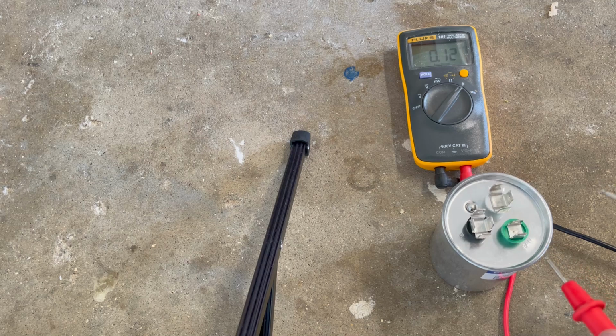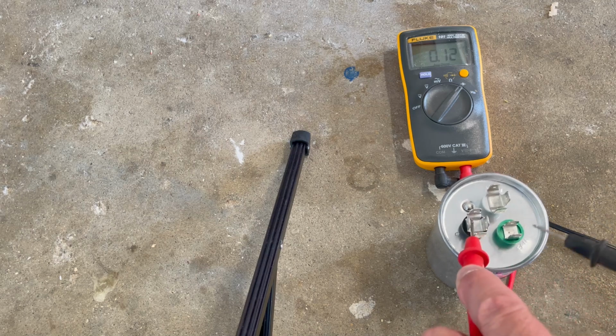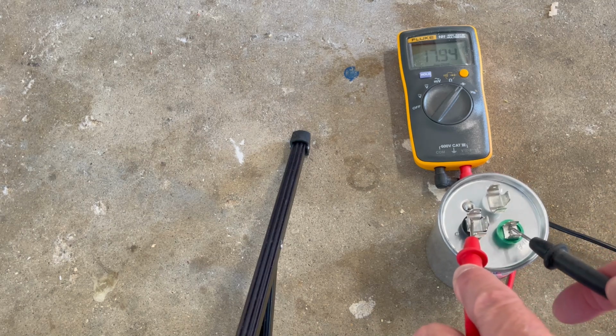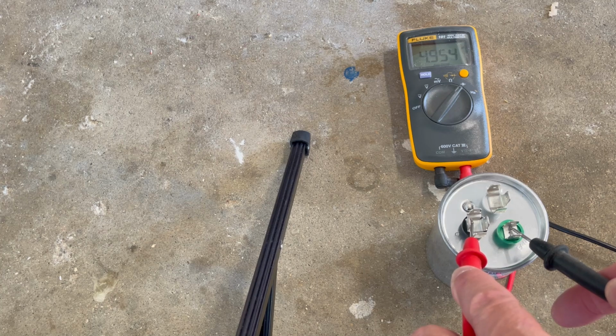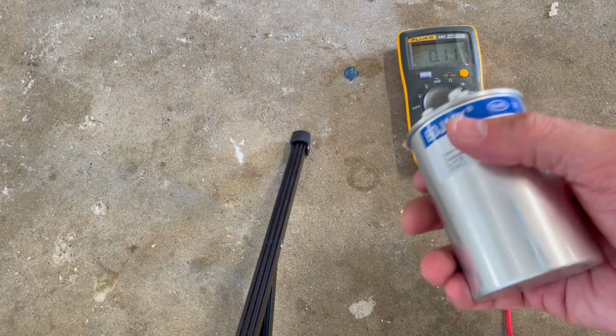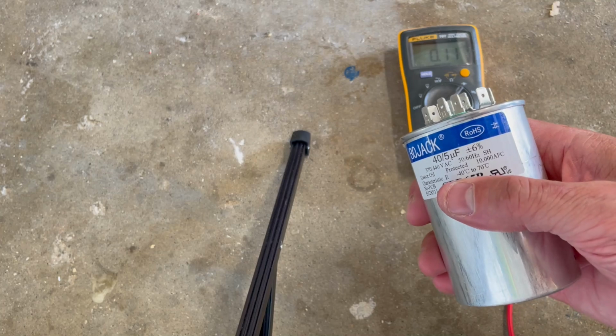Then we're going to do the same thing from common to fan, and this should be about 5. Yep, 4.95, so again we're within tolerances there. This looks like it's going to meet our needs as we get it installed. I'm going to go ahead and loosen up our bracket here.